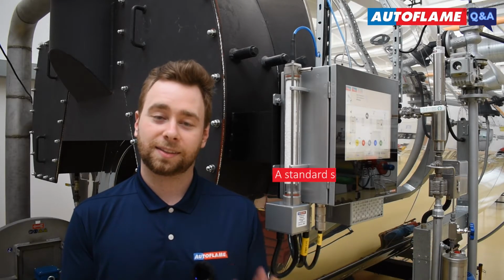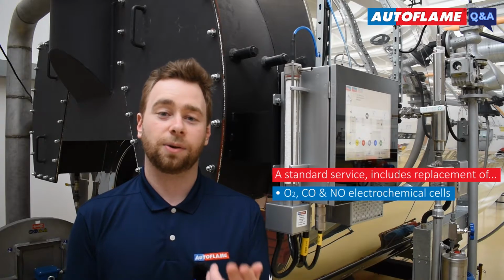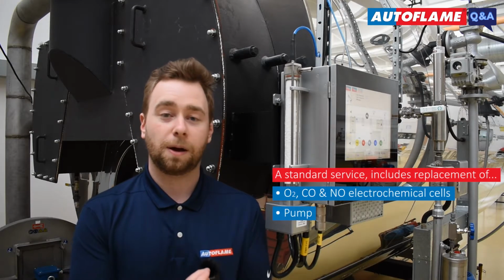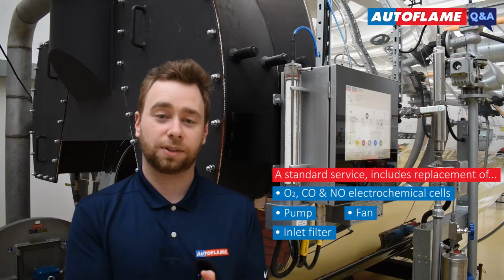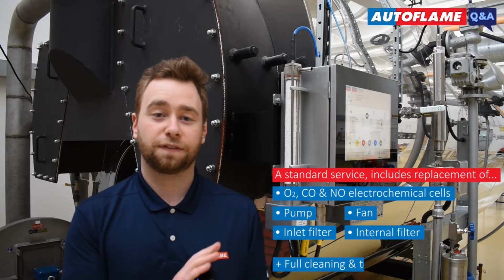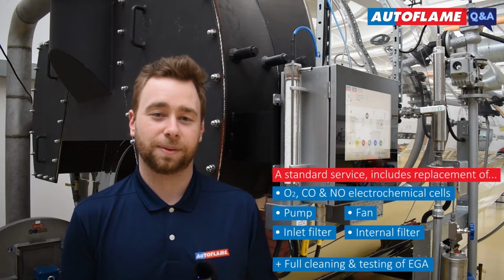Depending which fuels you're burning and your site conditions, the recommended EGA service interval can change. Typically for natural gas, we would recommend getting your EGA serviced every 12 to 18 months, but if you're burning oil, this reduces down to every 6 to 12 months. A standard service includes replacement of your O2, CO and NO electrochemical cells, plus your pump, your fan, your inlet filter and internal filter, plus full cleaning and testing of your EGA.